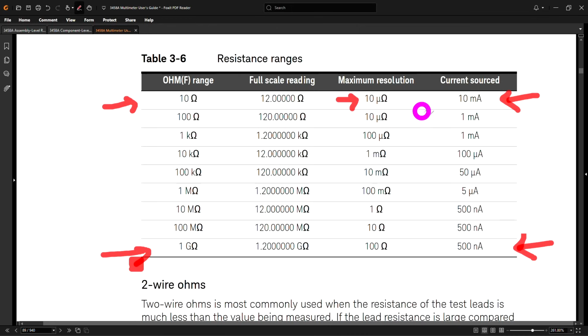And the instrument will dynamically change this current, and that's what auto ranging is. And how fast it can jump between these is the auto ranging speed, which you can measure on any multimeter, and it's something that people desire because if you're moving around a circuit, you want to quickly settle. So the way the settling works depends on the internal algorithm, but it shouldn't be too difficult. It will start from a certain current, it will measure the voltage. If it's over a certain range, then it will downscale into a smaller and smaller current until it gets the voltage it expects across the device. You can also force the range in a specific area and keep it there by removing the instrument from auto ranging, and that can push a specific current that doesn't jump around anymore. And sometimes it's advantageous, particularly at areas where it's really close to the transition between two of these ranges and there's an overlap in there.